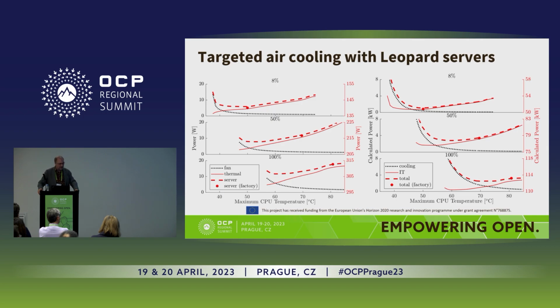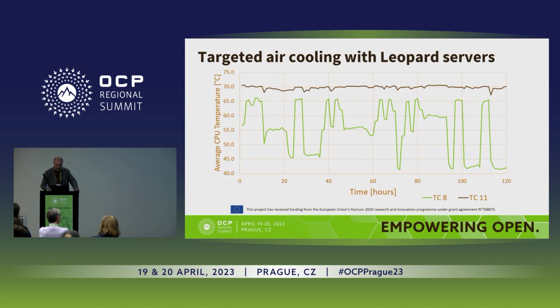So we actually spent a lot of time and money finding out that Facebook actually does a good job, because the servers are running at quite a good sweet spot. Here's an example of two workloads, exactly the same workload, run over 120 hours on the data center. One where we allow the BIOS to set the temperature of the CPU, so the fans are regulated by the CPU, and the other one is where we said, I want the CPU to be 70 degrees all the time. So you can see with the control of all of the fans in the data center, we were able to maintain a temperature of 70 degrees on the CPU, irrespective of the workload. So it's the same workload played twice for 120 hours, except one is with control of the fans, and the other one is just left to the BIOS.